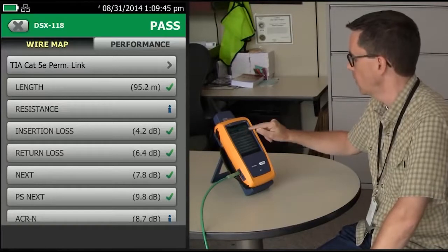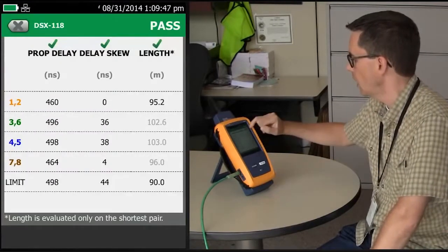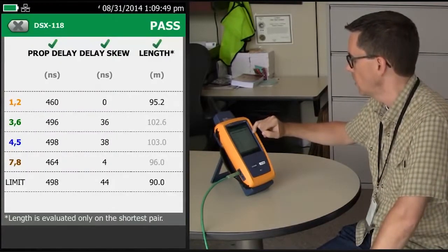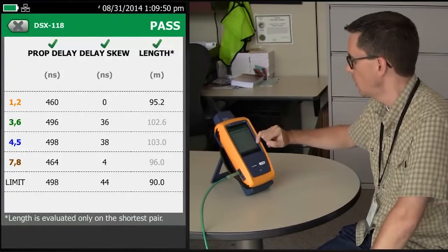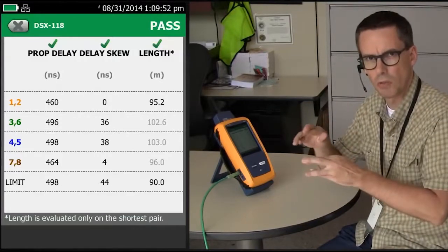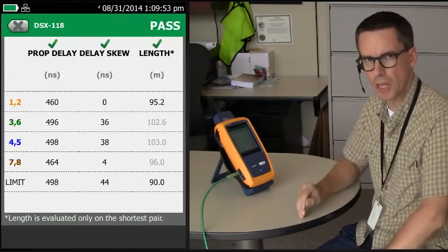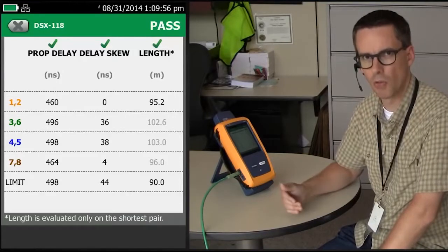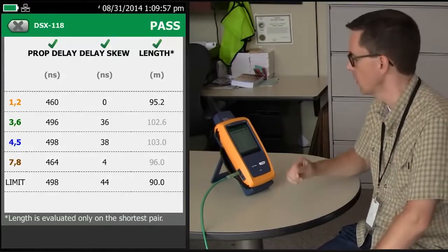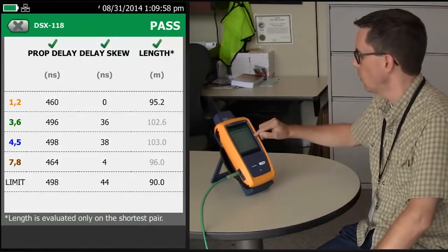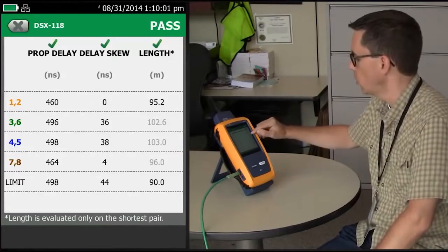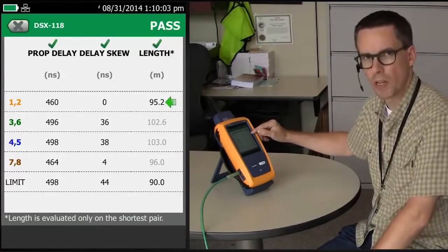If we tap here, we'll see our lengths. You get four different length readings because there are four different twists in the cable, and the standard requires us to do a pass-fail on the shortest length. So you'll find that three of them are actually grayed out, and the shortest one is the one that we're evaluating.